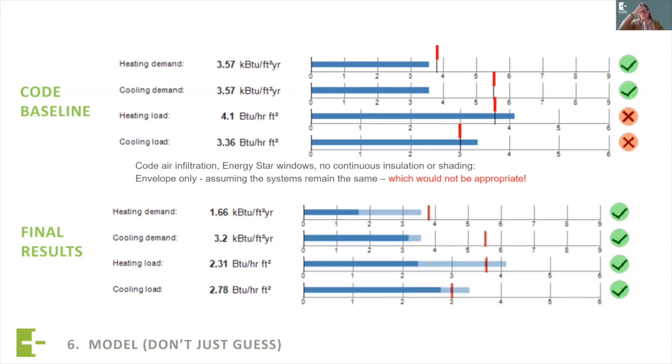And we can, in some cases, as with Finch, we really couldn't get there. That one front facade that you've seen many a time has solar shading on it because that's almost directly south facing. And there was no way to dial things in just with the window alone. So we added shading. But in many cases, depending on orientation, we can just work with the solar heat gain coefficient on different facades and get that cooling load down where we need it. It's a balancing act because if you increase that coefficient, you also increase the heating, but we usually have more wiggle room there.